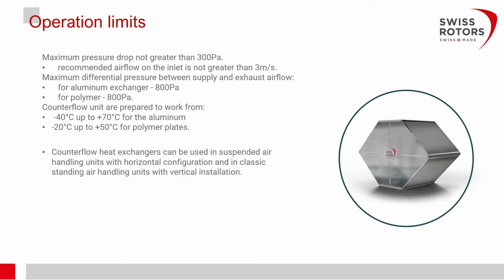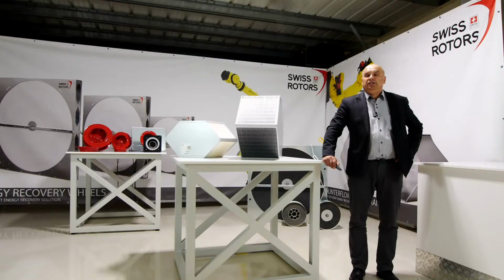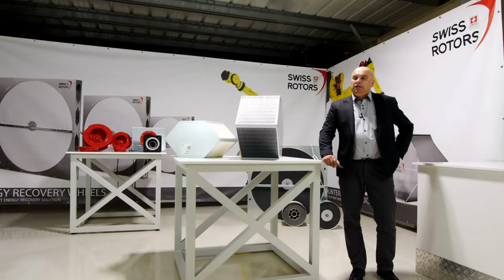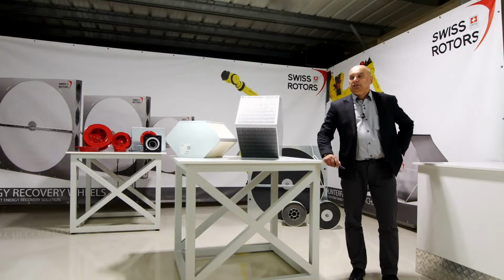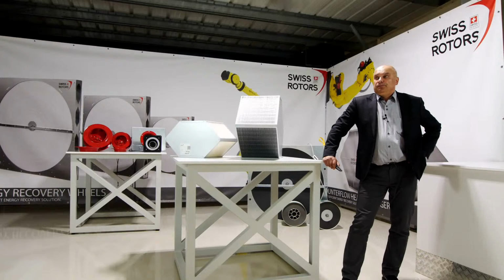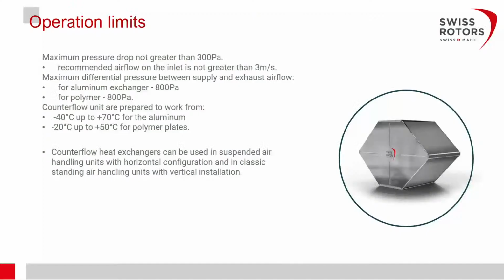And where can we use those counterflow plate heat exchangers? Usually this is very popular here in Europe for the suspended units when we do not have enough space above the false ceiling. Because the height of the exchanger is lower than the cross plate, but it's a bit longer. So it's not a problem to have a bit longer units, but we can save a lot of space in the height. But of course, if we properly install those units in the normal standing air handling units, it could be used also in the other one.